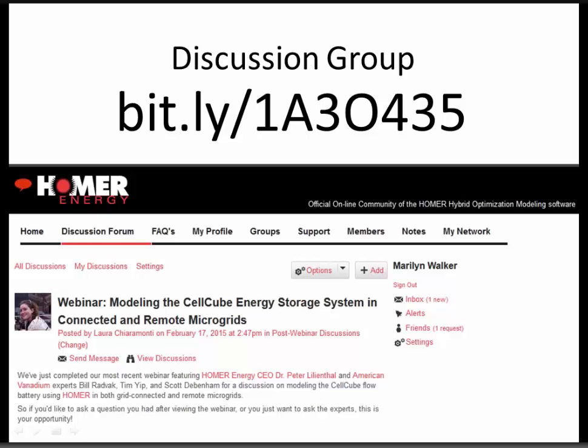The intelligence comes in the interface with either the microgrid or the actual grid, and that is in the inverter system. But the battery itself and the battery management really just works on a simple principle. If the voltage of the cell stack is higher than the load, it will discharge, and vice versa. So all you're trying to do is manage those with the battery management system.